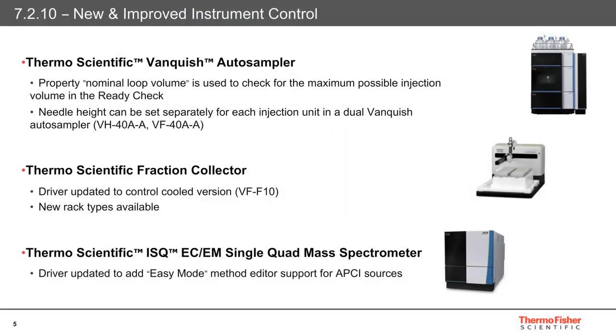Moving on to the Thermo Scientific Vanquish HPLC instrument, a new updated driver for the Vanquish Auto Sampler has been released. This introduces a new property called Nominal Loop Volume, which is used to check for the maximum possible injection volume in the Chromeleon CDS Ready Check. It's also possible to set the needle height separately for each injection unit in the dual Vanquish Auto Sampler, expanding on its current application capabilities. We've also updated the VF-F10 driver used to control the Thermo Scientific Fraction Collector, which now adds support for the cooling configuration, including capacity for five new associated rack types. This ensures that sample integrity is maintained for temperature sensitive and precious compounds.